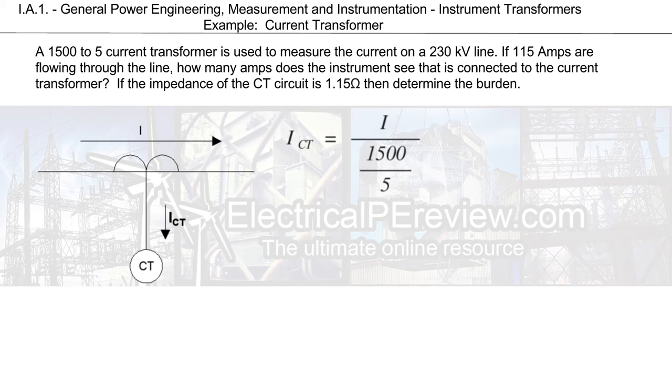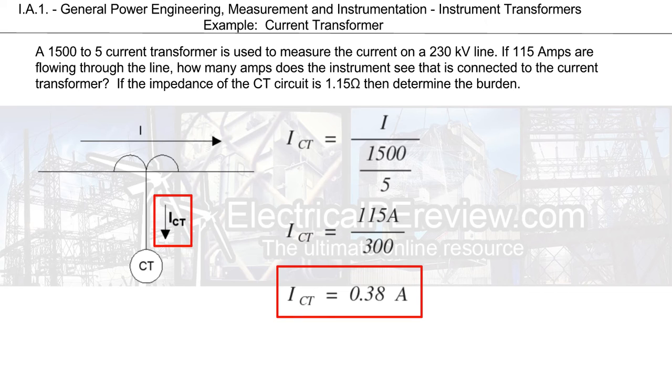So to start things off, we're going to find our current going to our CT by dividing the line current by our ratio of 1500 to 5. Our line current here in this example was given in the problem statement as 115 amps. Solving for our secondary current or our current transformer current, we're going to find 0.38 amps. And that is the current being derived through the windings of the CT off the primary line.